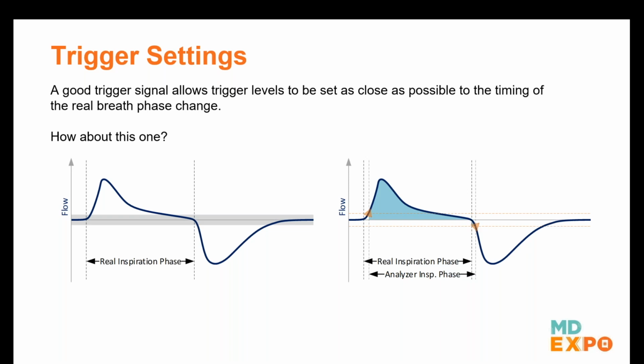However, you see in this example the waveform is not as steep as in our first example. That again means that we are missing a little bit of timing here, and it adds a little bit more inspiratory time at the end. For all our timing-based parameters, like rate or inspiratory time, this is not going to have a big impact because the actual length is still the same. It's just a bit shifted in time. But for the volume calculations, we are going to miss a little bit of volume here, and we're going to count a little bit of volume as negative over there. So this is a good trigger signal, but still not ideal.